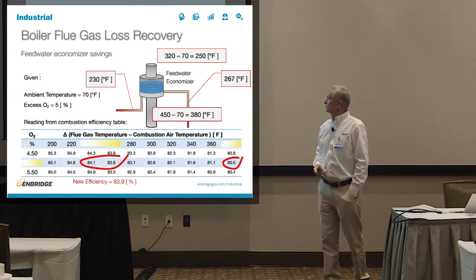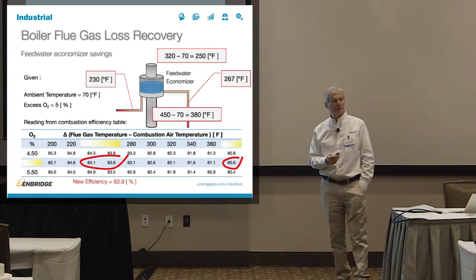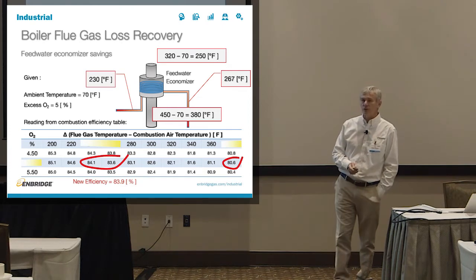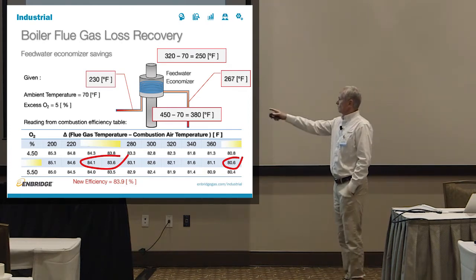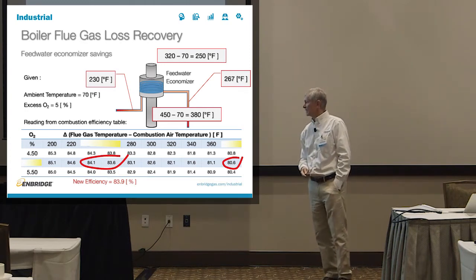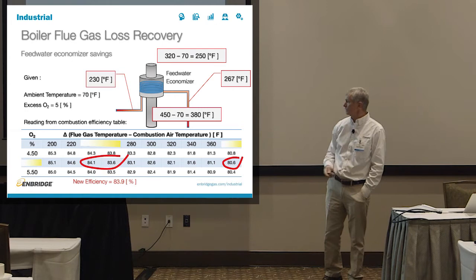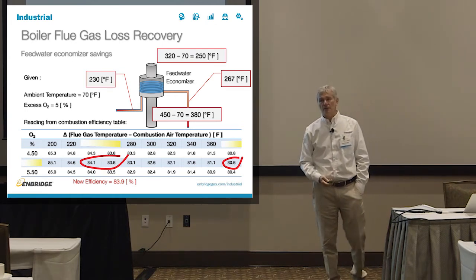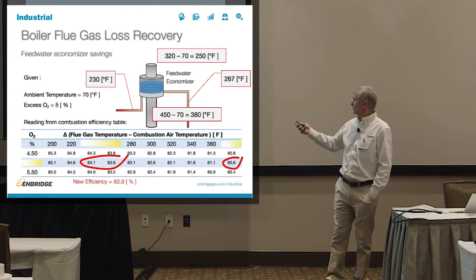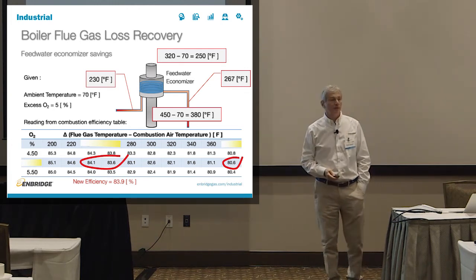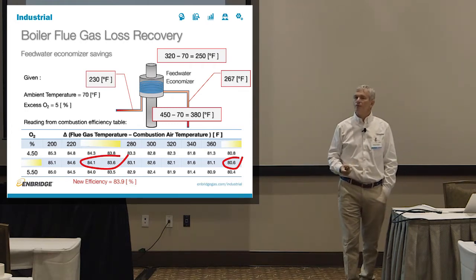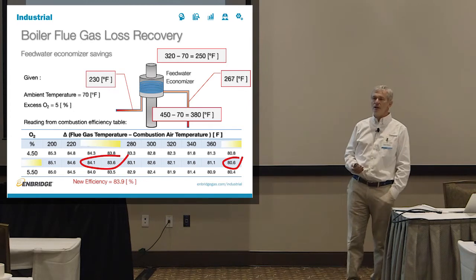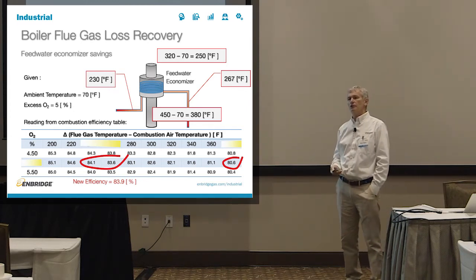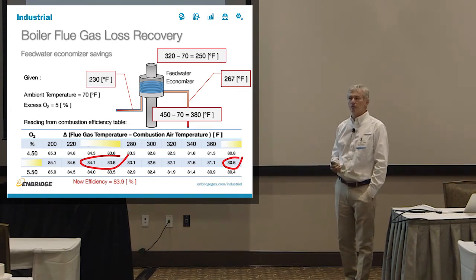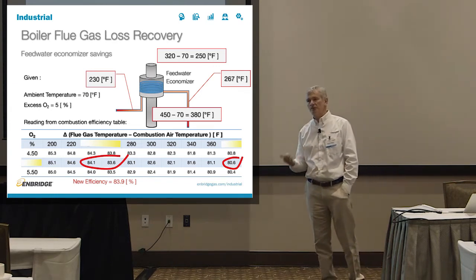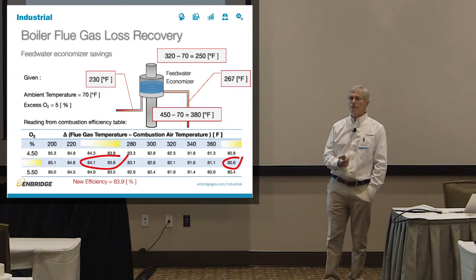So after the feed water economizer, you have 320 degrees F, remember in that example? We subtract the ambient temperature and get 250 degrees F. That puts us on the chart between 240 and 260, and if we extrapolate the efficiency at 5% oxygen, you get a new efficiency of 83.9%. So by installing the feed water economizer, you have improved the efficiency by about 3% automatically. The rule of thumb that we always use is that a feed water economizer can usually recover about 3%. In a really good application, it can recover about 5%. So if somebody is selling you a feed water economizer and says you're going to save 15%, talk to us. It's probably not possible.